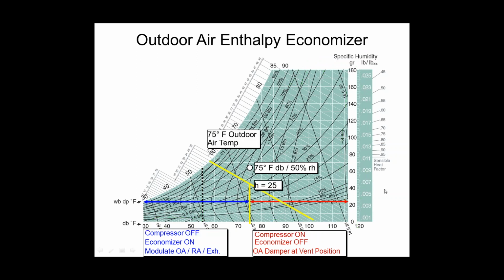If I have an enthalpy economizer, then what I have is this angled yellow line here, right? So I'm looking at enthalpy, which is temperature and humidity combined. And if you're familiar with the psych chart, these lines over here on the left are my enthalpy lines. So right now I've set this guy for 25 BTUs per pound of dry air for my enthalpy, and that line goes across like that. But I don't want to take a day where it's 95 degrees out just because it's dry. That's way too hot. So I also have a temperature cutoff, in this case by code of 75. So if anything's below the angled line and to the left of the vertical line, this whole region over here that I just circled, that's going to be my economizer day.